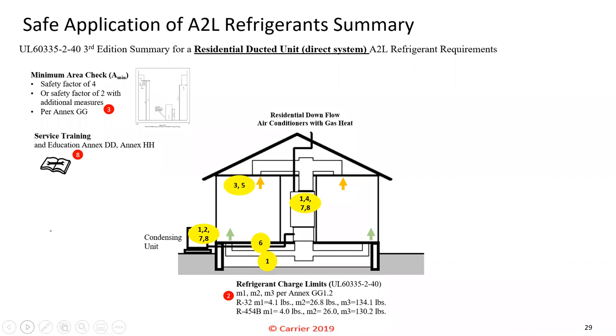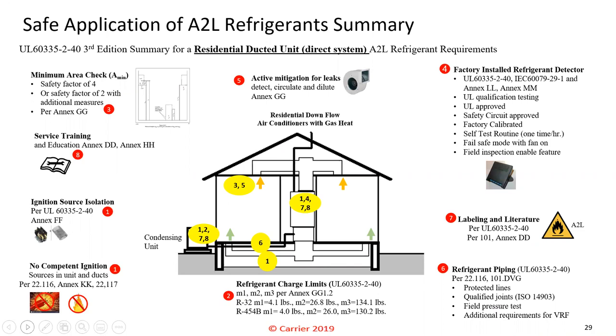So this is a visual representation of what a product safety standard looks like or covers, specifically for A2L equipment. Now there are multiple ways to skin this cat, so to say, because every product type may have its own specific set of requirements that are specified in the standard. However, one thing is common across all. The safety standard tries to reduce the probability of refrigerant leaks. And when it does leak, it reduces the potential for ignition and a severe event.